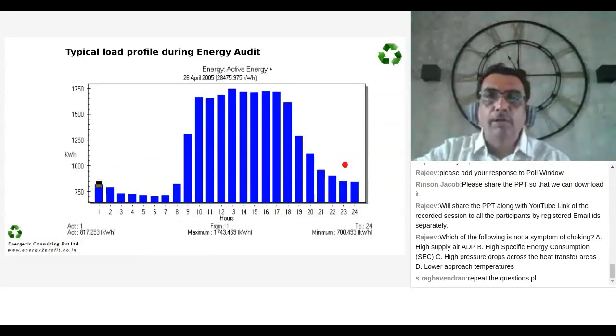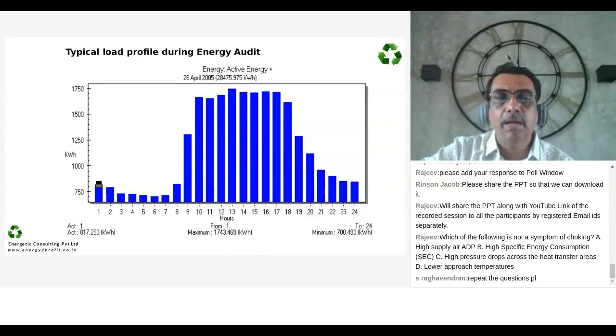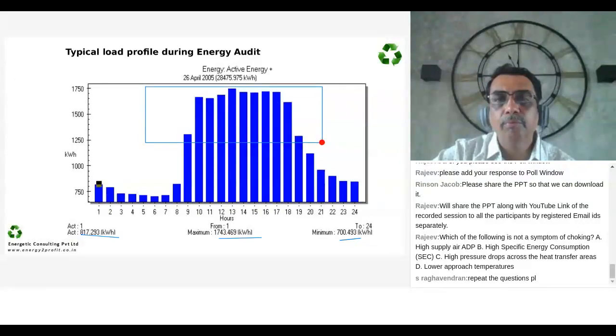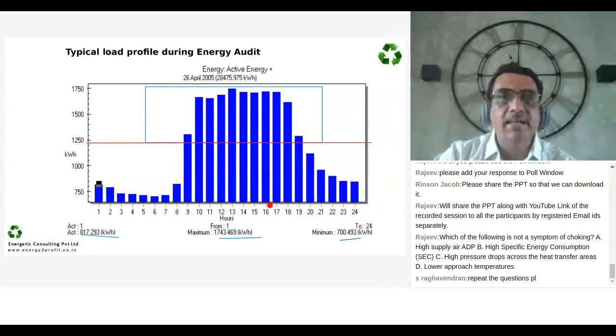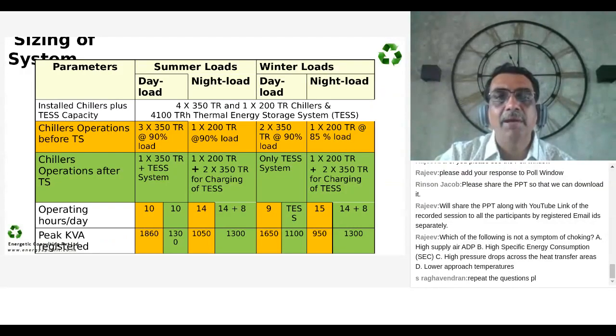This was the profile we logged during the typical energy audit, hour on hour kilowatt basis. This is the maximum kW. This is the minimum. These are actual measurements. So what we are trying to do, I'll just repeat again: I'm trying to cut this portion off. I'm trying to run this system at an average, and I'm showing you something which actually happened. This is not theoretical. We could manage to get 600 kilowatt of reduction in this system on a maximum demand basis.